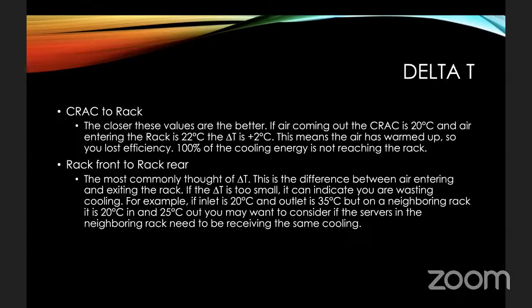And if I've got 40 coming out, I've obviously got a problem. My cooling is not working, right? So something is going wrong inside of that rack. If I've got 20 coming in, I've got 25, 30 degrees coming out, then everything's okay. So monitoring the delta T not only helps you identify hotspots, but it can also help you identify how efficient your cooling system is, which I will illustrate shortly.